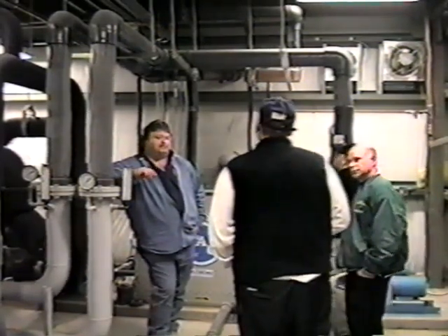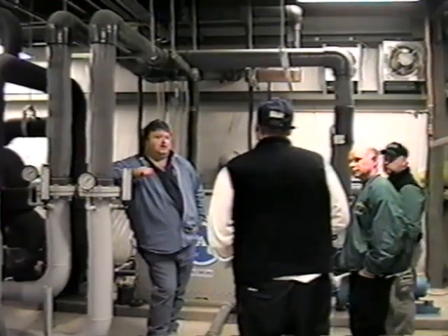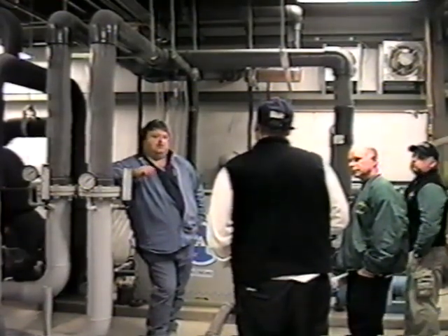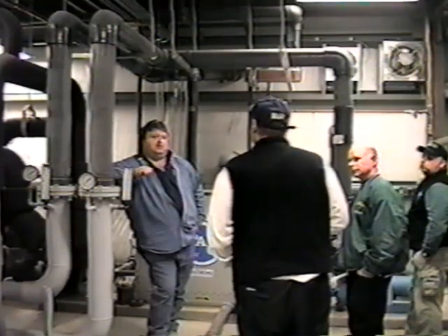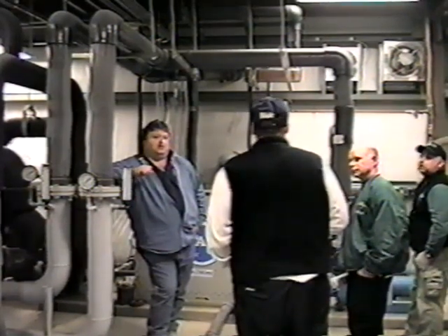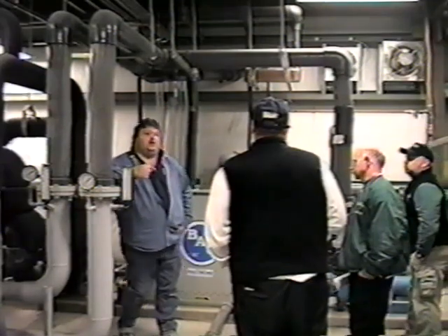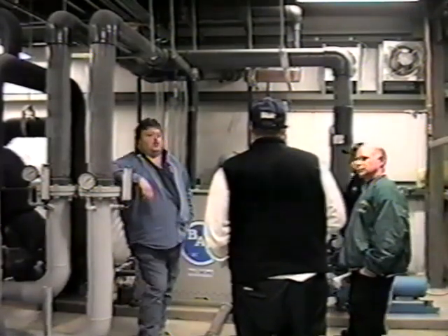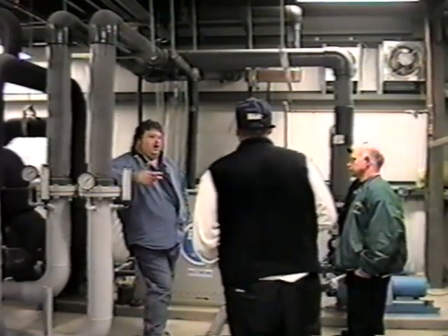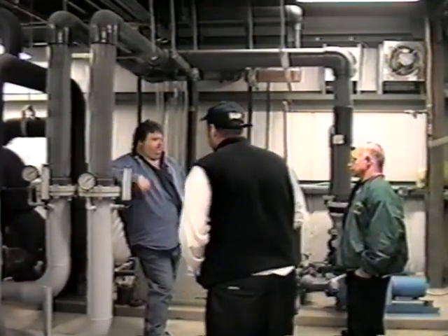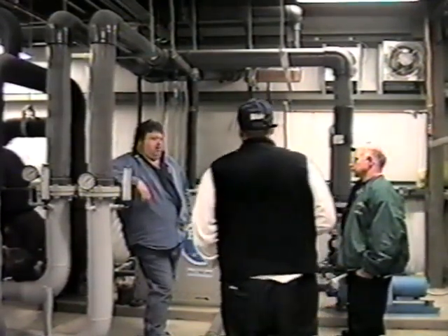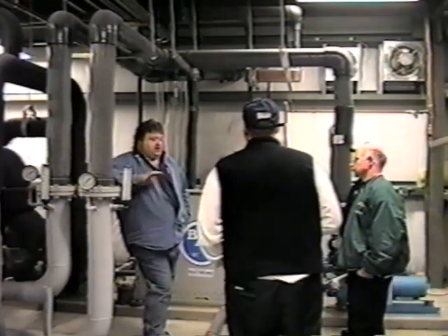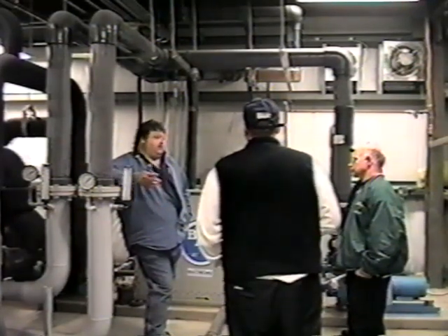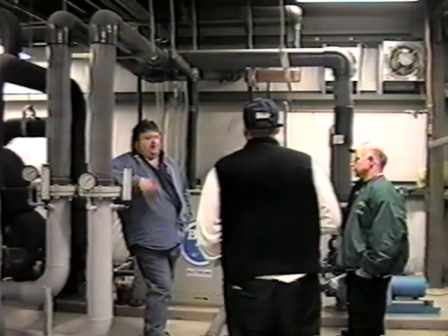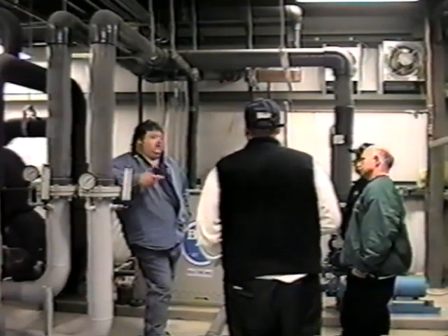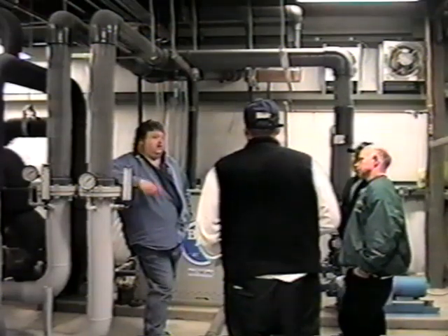Now, what was it when we used to have to purge the system in Clinton? And boy, you get the smell. Is that ammonia? Yeah. Well, with ammonia, that's totally different. There's times when you get air in the system, and you have to burp the air out. And ammonia is a much better, actually, energy efficient refrigerant and everything. Problem is that a lot of people are scared of it. I prefer it. When it leaks, you know it.